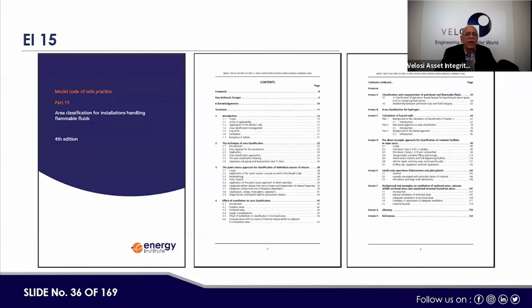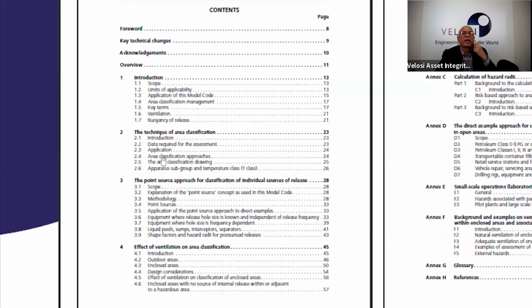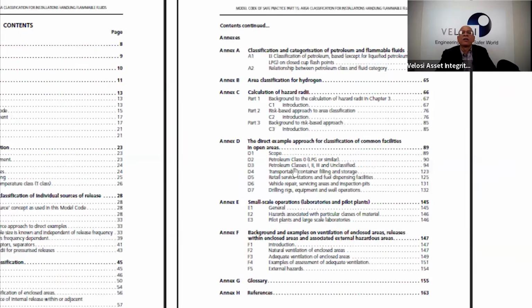Now, if we try to see these standards, what is covered there? This is IP-15 or part 15. So here, what we normally go through: the technique for area classification, the point source approach for classification of individual sources of release, then the effect of ventilation on area classifications. Then their appendices also cover the classification and categories of the petroleum and flammable fluids. Then area classification for hydrogen, calculation of hazard radii, then the direct example approach, then small scale operations and so on. So this standard, basically, if I say, we have been using for a long time and it's quite basically an easy to use standard.